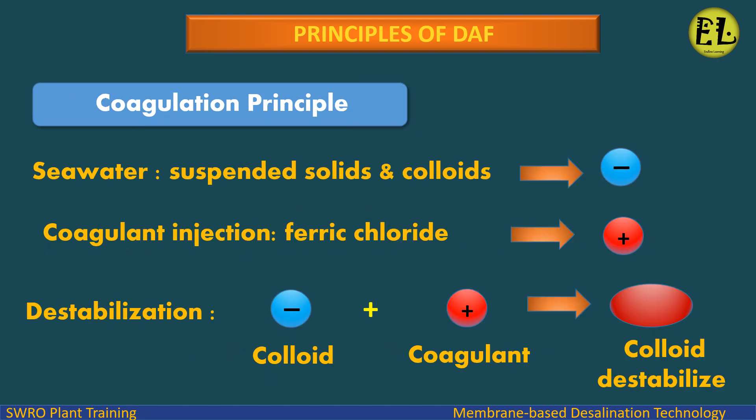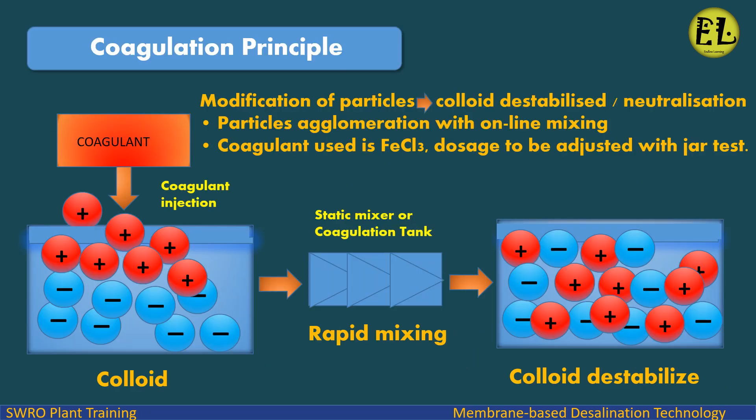Coagulation principle: Seawater suspended solids and colloids carry a negative charge. Coagulant injection — ferric chloride (FeCl3) carries a positive charge — causes destabilization: colloid plus coagulant yields a destabilized colloid. This modification of particles leads to colloid destabilization and particle agglomeration with online mixing. The coagulant used is FeCl3, with dosage to be adjusted via jar test.